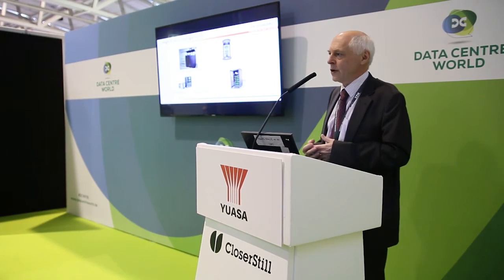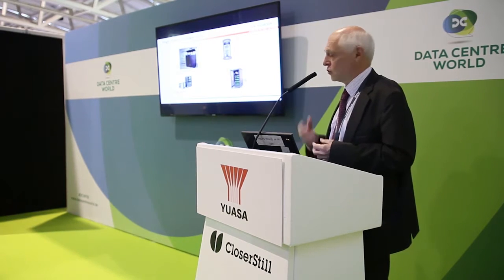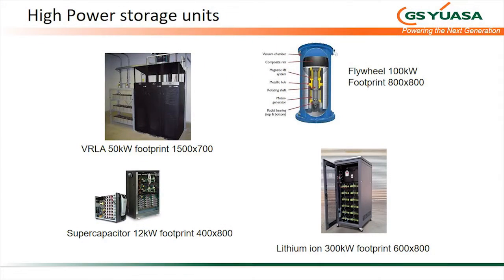So how does that compare with other high power options that you have for UPS or storage units? These are the main types that you can just pick up from commercial applications. VRLA, over on the far left, for 50 kilowatts, that set of batteries had a footprint of about 1500 wide, 700 millimeters deep. A flywheel, this is a 100 kilowatt flywheel, footprint 800 by 800 millimeters. Supercapacitor, that was a 12 kilowatt off the shelf thing with 400 by 800. Fairly low, they could be taken higher, but that's something which is on the market.